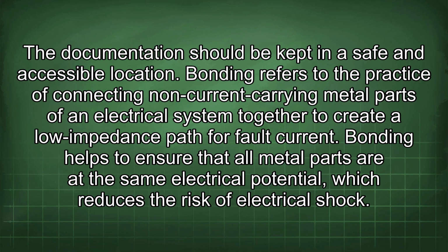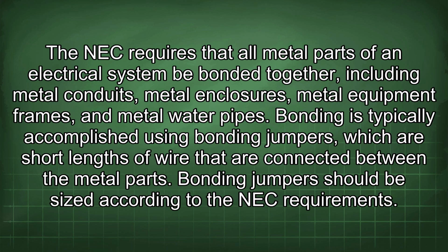Bonding refers to the practice of connecting non-current carrying metal parts of an electrical system together to create a low impedance path for fault current. Bonding helps to ensure that all metal parts are at the same electrical potential, which reduces the risk of electrical shock. The NEC requires that all metal parts of an electrical system be bonded together, including metal conduits, metal enclosures, metal equipment frames, and metal water pipes.